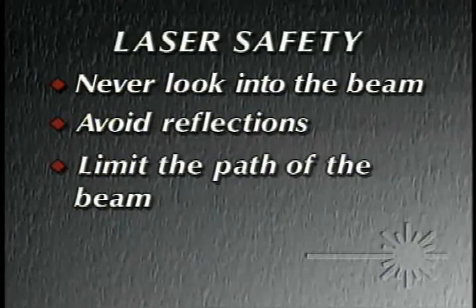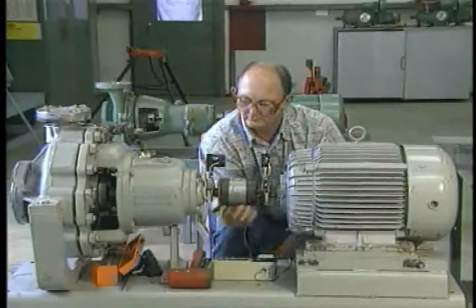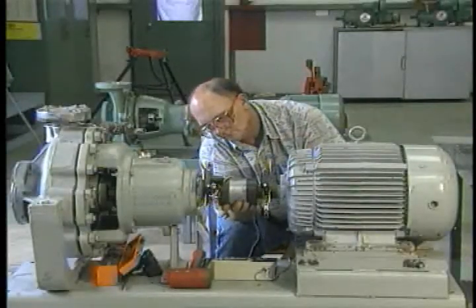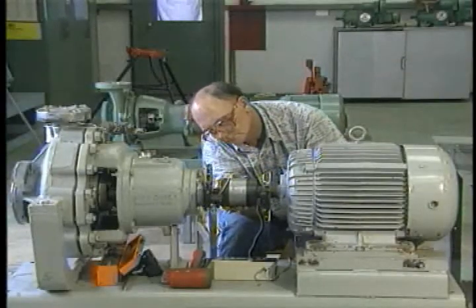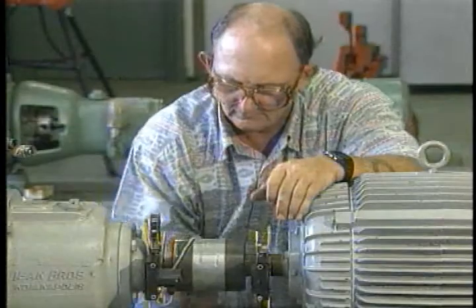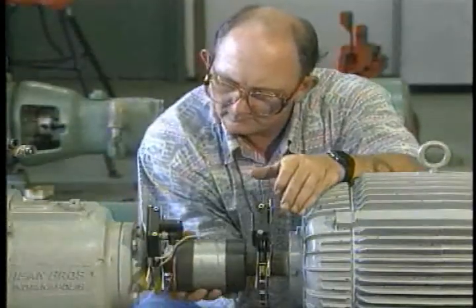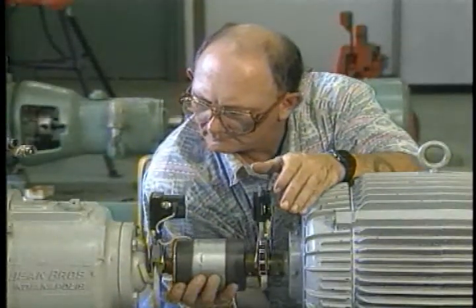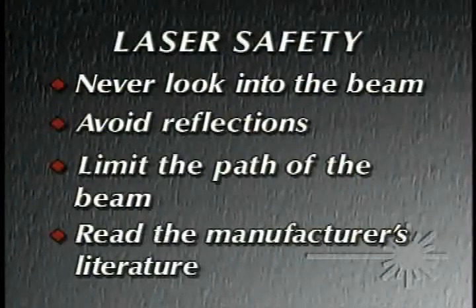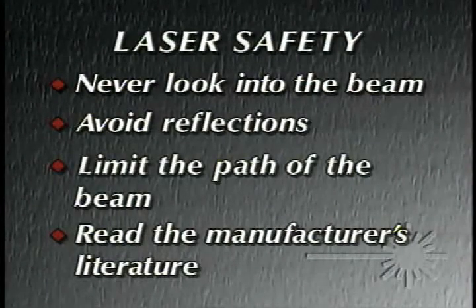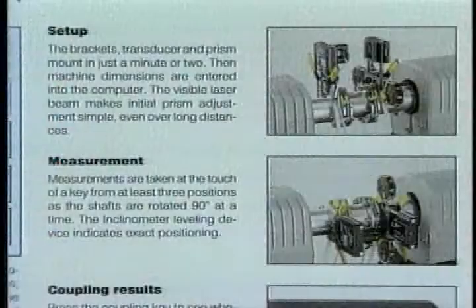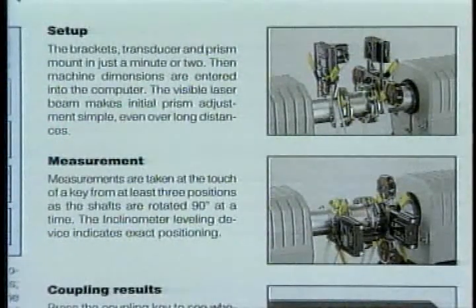When rotating shafts with the laser equipment turned on, always rotate both optic heads at the same time so that the beam cannot escape. And do not operate the laser with only one optic head in place. A stray laser beam is a potential hazard. And fourth, read the manufacturer's literature. You should always be familiar with equipment-specific instructions and precautions provided by the laser manufacturer.